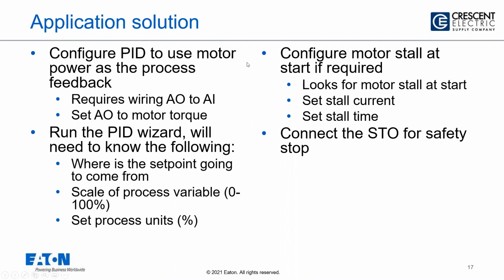So in this application, how do you use it? There is a PID that is available, and you can use that to control the motor speed. And the feedback, the set point, and here it is a torque set point, so you bring the horsepower set point. You set it through either analog input or through fieldbus, but you bring your torque feedback or your horsepower feedback into the drive. You have to wire an analog output, map it to the torque feedback or your horsepower feedback, and then bring it to analog input, and that becomes the PID feedback, and the motor speed is automatically adjusted based on the PID gains that we set for the PID.